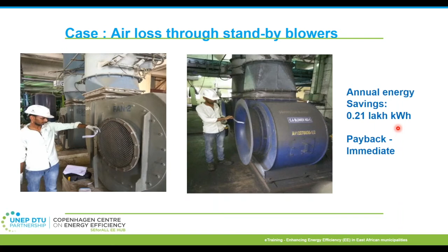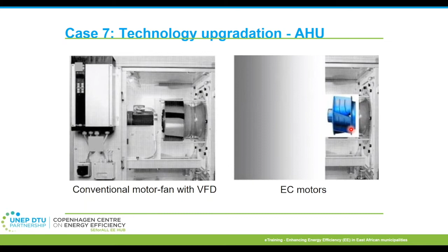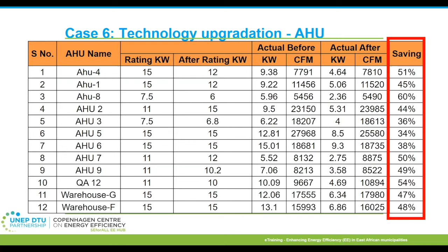You can also go into technology upgradation, such as variable frequency drives for fans. Lately there are better technologies like EC motors, or electronically commutated motors. Compared to a setup with a VFD, a motor, and a blower separately, this technology is compact and concise within one small space. It's quite efficient and emits less noise. Based on field results, before and after the new technology implementation, power consumption drastically reduced while maintaining the same flows, achieving 36% to as much as 60% energy savings.